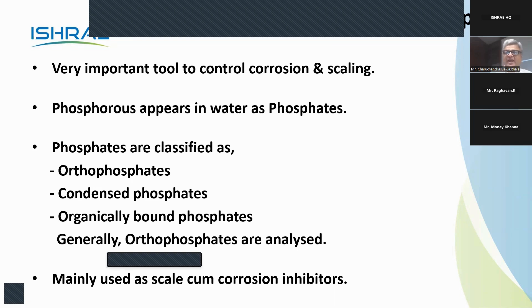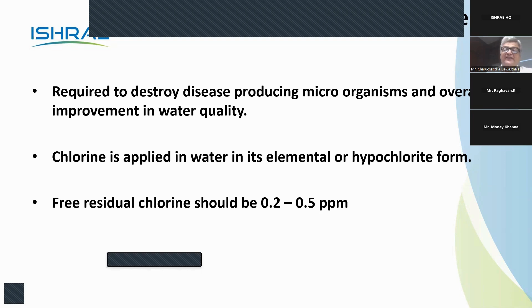There is a saying in the market that free residual chlorine should be kept a little on the higher side. Normally it is kept at 0.2 to 0.5 ppm basis, so barely some chlorine, but sufficient chlorine is there. Chlorine is applied to water in elemental form, as chlorine gas, or in hypochlorite form, NaOCl, OCl form. In both cases, it can be calculated how much chlorine is dosed so that the free residual chlorine (FRC) should not cross 0.2 to 0.5.